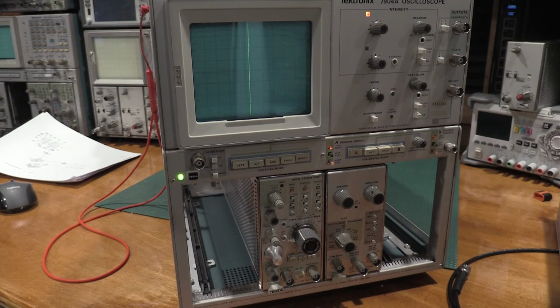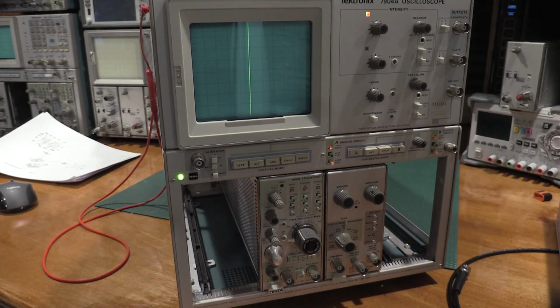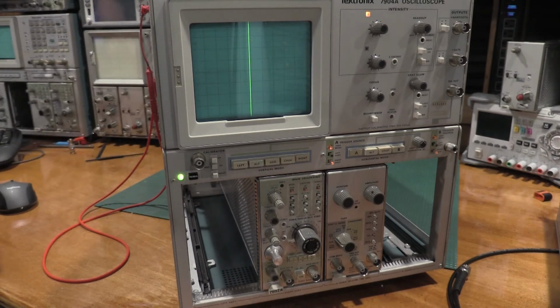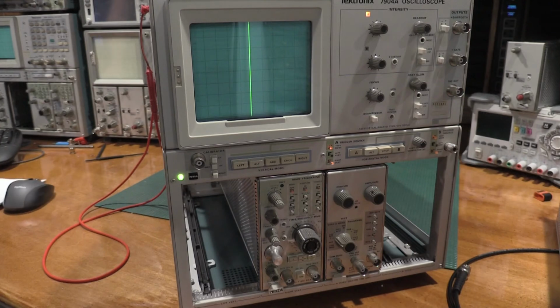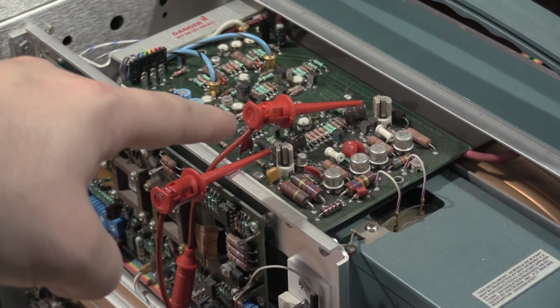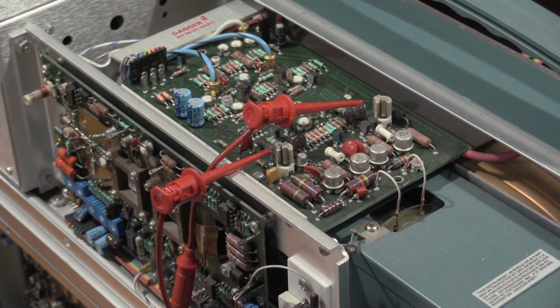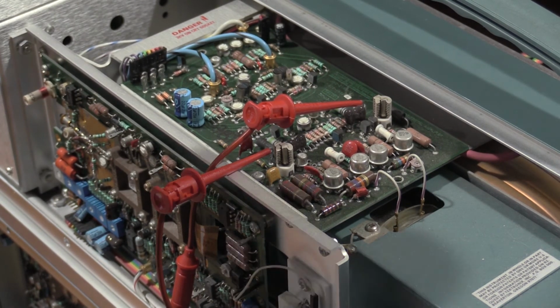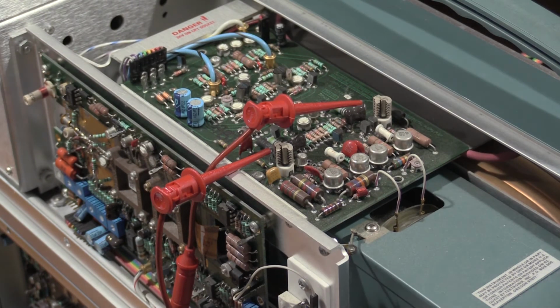Okay, here's the test setup for the limit centering, which is R630. After shorting test points 610 and 750, we should be within 0.5 divisions of the center line. We are, but it will need adjustment. Here's the shorting points. All right, up here's the horizontal board, down here's the vertical board. So the vertical board's the one that has more of the high-speed exotic stuff on it, because that's faster than the horizontal. But those are the 2 test points you short out next to the adjustment capacitors.